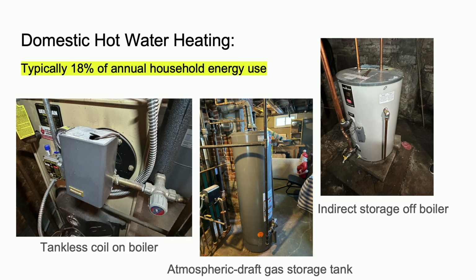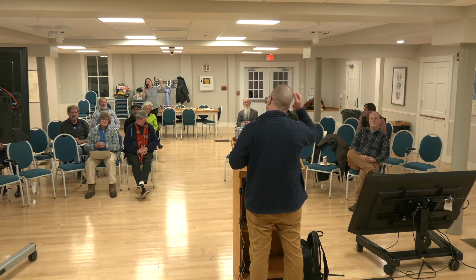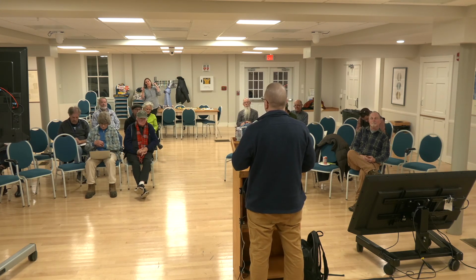Colin, how does that play out with wood stoves? Is there a minimum number of air changes below which you don't want to go if you do have a wood stove? Well, definitely 3. Certainly 3. I would say even probably 5 air changes per hour is getting pretty tight at that point. You can bring in a ducted air system to bring fresh intake air to a wood stove, but usually what that looks like is a duct that runs in from the outside and then stops right next to the wood stove. So you just get cold air coming right in through the duct. So what's the point of building a tight house if you're going to put a giant hole in it? Yeah.